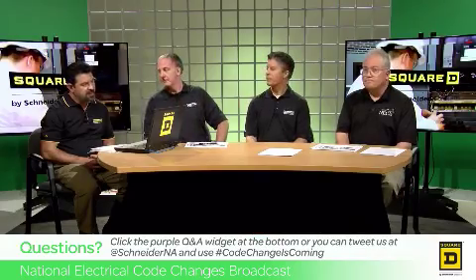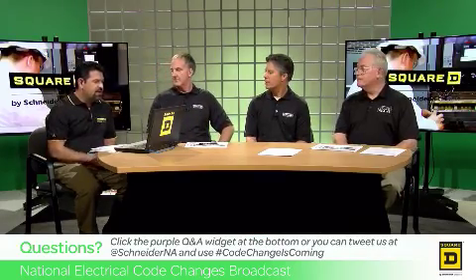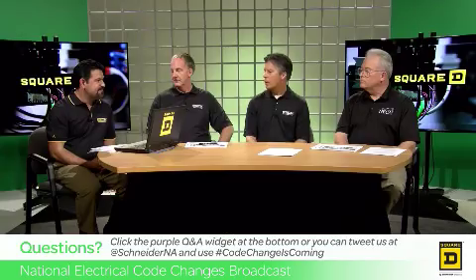Great. Next question. Does 408.3(A) make the panel a non-live work situation if the main breaker is off and I have arc flash protection on? So the requirement in 408.3 does provide electrical shock protection. There were areas in the country where particularly the utilities really frowned on pulling the utility service meter away. So yes, if you do have the main breaker off, in a single main breaker application you wouldn't be exposed to line-side bus. And that's really the intention here. It is an electrical shock protection.